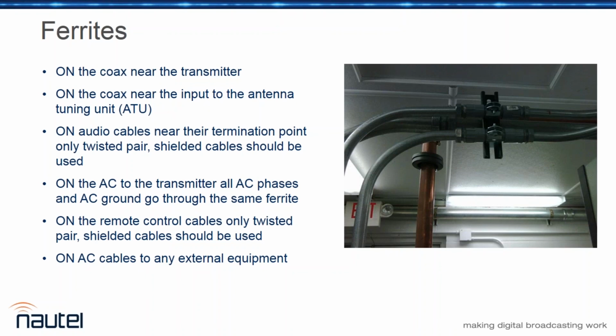But in conjunction with good grounding and good surge protection, a ferrite can be the difference between having failures and not having failures. Remember that what we're dealing with, as we come back from the antenna to the AC lines, is lightning protection as a voltage divider theory. We look for all the places lightning can go, make the path through the surge protector between the ground and the AC lines the lowest impedance path, and raise the impedance of everything else wherever we can. Adding ferrites is one way to do that.